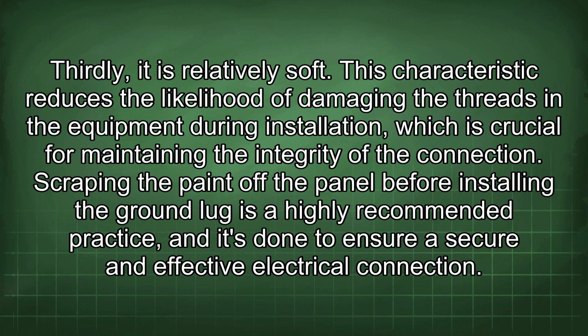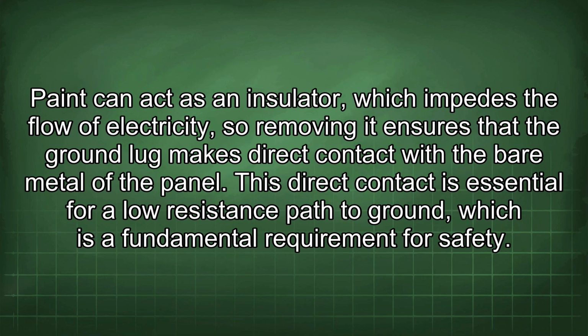integrity of the connection. Scraping the paint off the panel before installing the ground lug is a highly recommended practice, and it's done to ensure a secure and effective electrical connection. Paint can act as an insulator, which impedes the flow of electricity, so removing it ensures that the ground lug makes direct contact with the bare metal of the panel. This direct contact is essential for a low resistance path to ground, which is a fundamental requirement for safety.